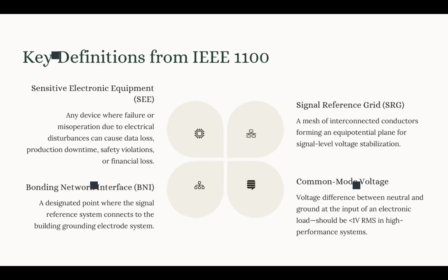Another definition is bonding network interface, BNI. Okay, that BNI is the designated connection point where the signal reference system, that SRG that we talk about, interfaces with the building grounding electrode system. Sorry, the BNI is the point where the SRG connects with the building ground electrode system. So that point is where the SRG is connected to our facility ground.